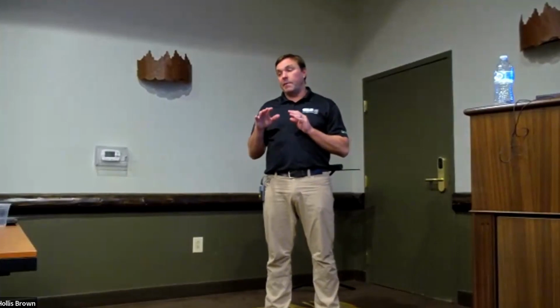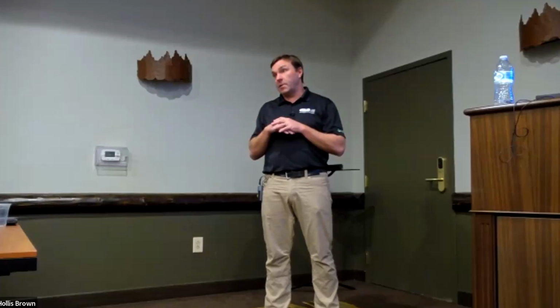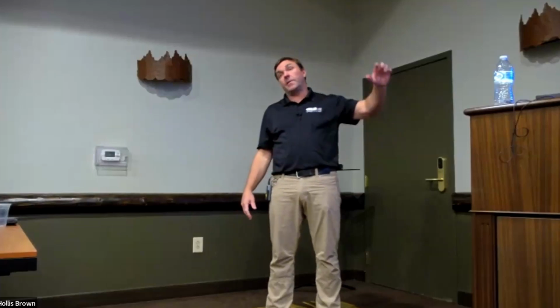And typically when issues occur, it was an installation issue. The poly wasn't done right. The spray foam wasn't done right. The termite strip wasn't done right. The application really is everything when it comes to all these systems. Because to the earlier caller's point, you are taking an existing house and you are changing it by putting a conditioned crawl under it. You're changing it by putting an unvented attic. So you better be doing it right if you're going to make changes to the house. Is that it? Move on.